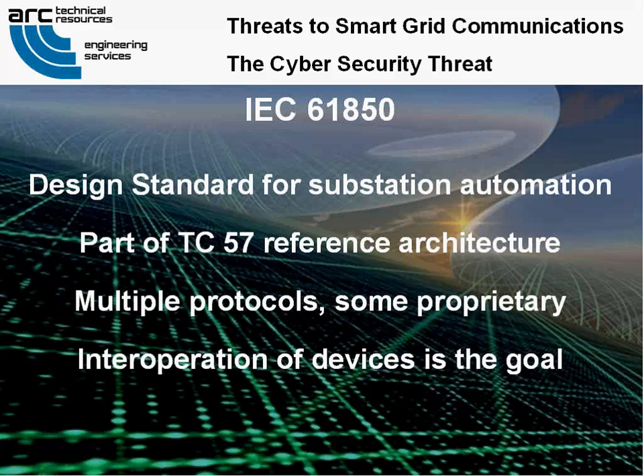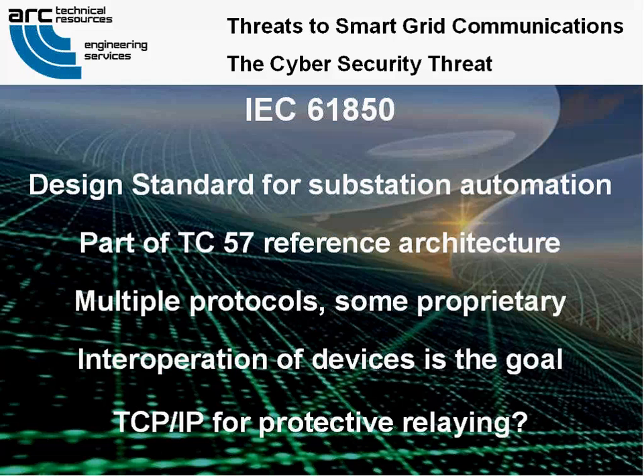Current mappings in the standard are to MMS, GOOSE, SMV, and soon to web services. These protocols can run over TCP/IP networks and/or substation LANs using high-speed switched gigabit Ethernet in order to obtain the necessary response times of less than 4 milliseconds for protective relaying. But you'd have to be out of your tree to use IP for relaying unless the local relay also was able to open that contactor in case you didn't get your signal. You wouldn't want to fry the transformer.